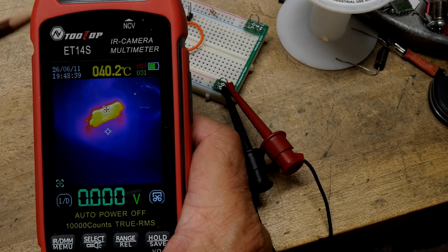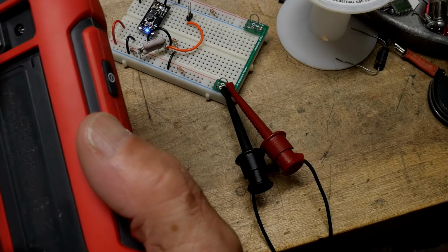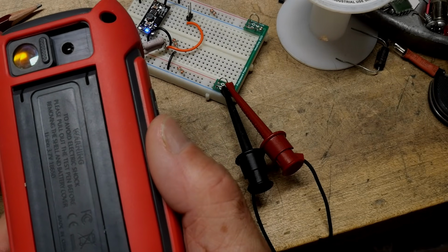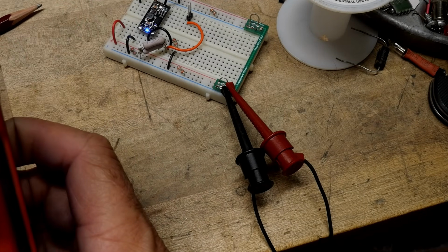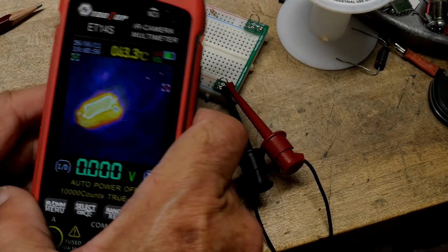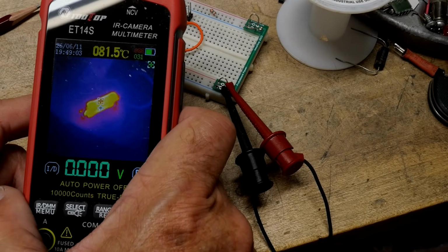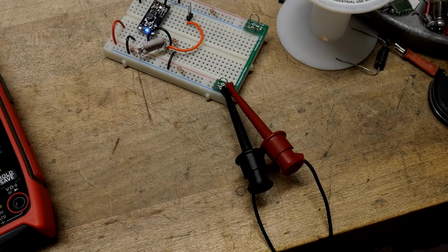I had one question from a viewer. He says, well, if you don't have a macro lens, can you just use one of those little clip-on lenses you put on your iPhone? No. It has to be zinc selenide, zinc sulfide, or germanium. It's got to be one of those, right? And this one has, we'll flip it in, a nice close-up lens, so we can look really, really close at that hot object. Okay, there you go. All about IR lenses.